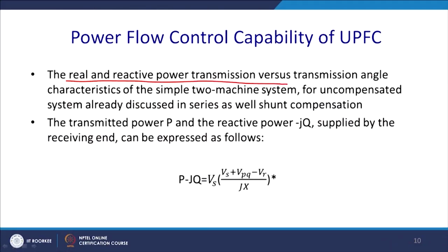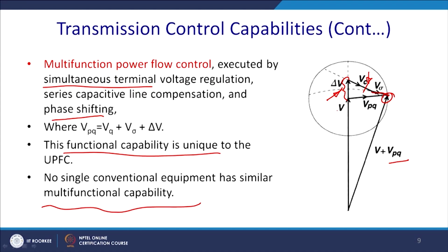We see that it is a quite versatile device, so how does the power flow, and how can it be controlled? For the real and reactive power transmission versus the transmission angle characteristics, we have to go back to our two machine model. The characteristics of the simple two machine system for the uncompensated system were already discussed in series and shunt compensation. That same will be the takeaway, because it depends on which mode of operation you select. If you select this mode of operation, which is basically the tap changing transformer, that equation will come into the picture. If you take this mode of operation, then it is the SSSC's operation, and if you say V sigma operation, that will be the PAR operation, and accordingly the rating will change.